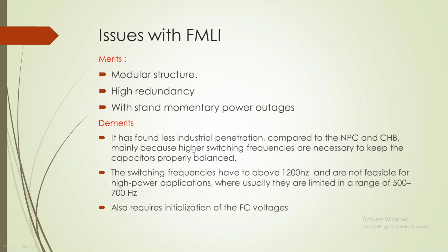So I have to go for higher switching frequencies. The switching frequency has to be high. It will go up to 1200 hertz or above for the flying capacitor multi-level inverter to balance the capacitor voltages. So this is a drawback of the flying capacitor model. Going higher than 1200 hertz at power level is not acceptable. It is limited to only 500 to 700 hertz. So flying capacitor multi-level inverters are not actually gaining industrial applications in the market.